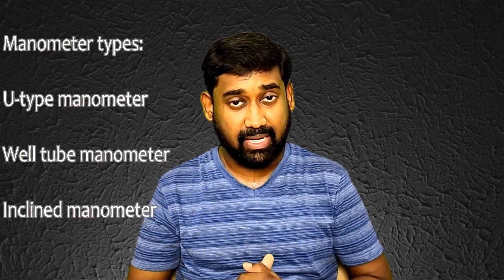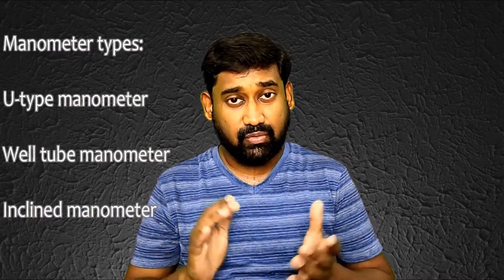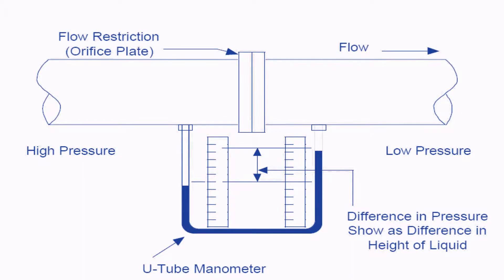We have different types of manometers: U-type manometers, well tube, and inclined manometers. For example, you can see in this figure — there is a pipe with an orifice plate, which is a restriction. In the upstream of the orifice plate we have high pressure; on the downstream we have low pressure. Between the high and low pressure we have tappings connected to a U-tube manometer. Due to the high pressure in the HP leg, pressure is exerted on the liquid, pushing it to the LP side. You can see the difference in the liquid head between them, and this is the differential pressure — this is how a U-tube manometer works.